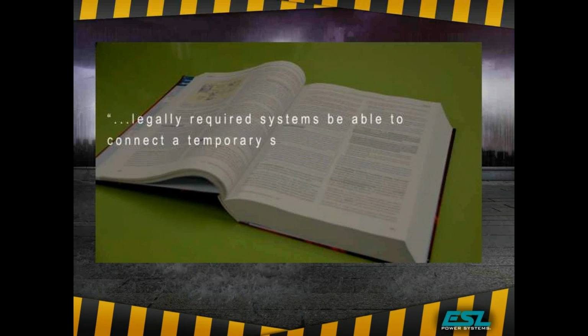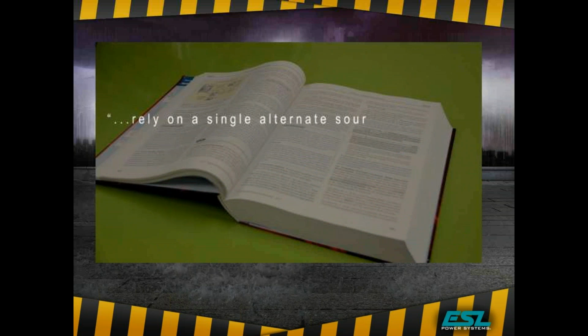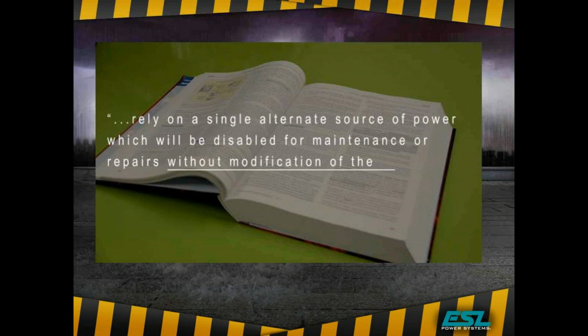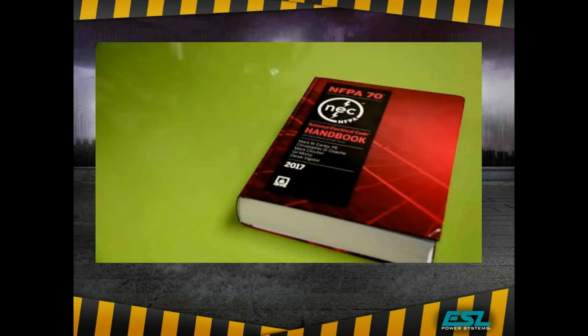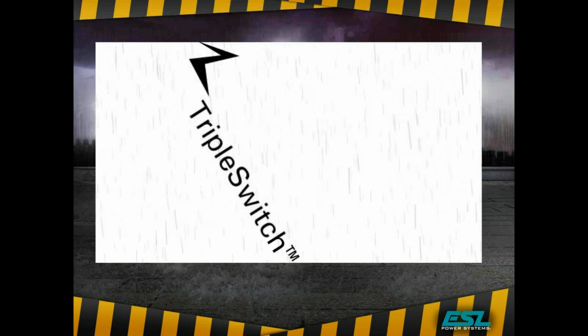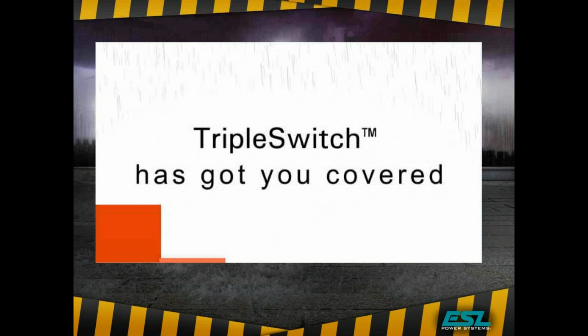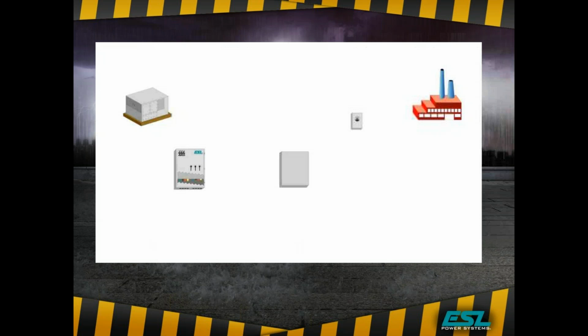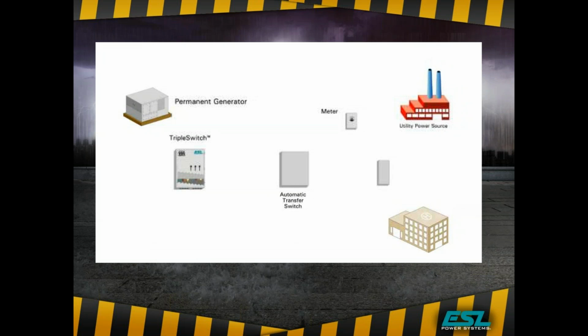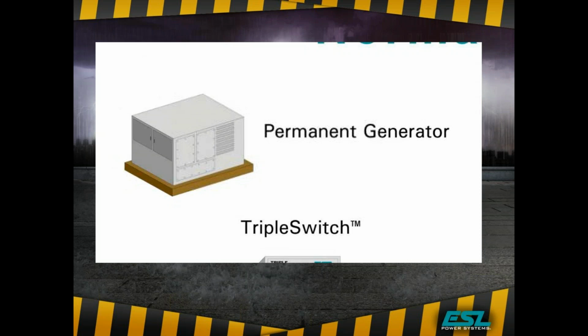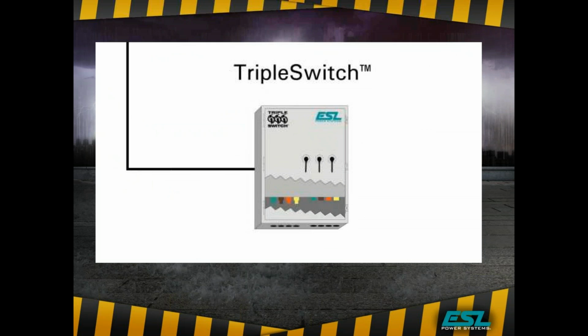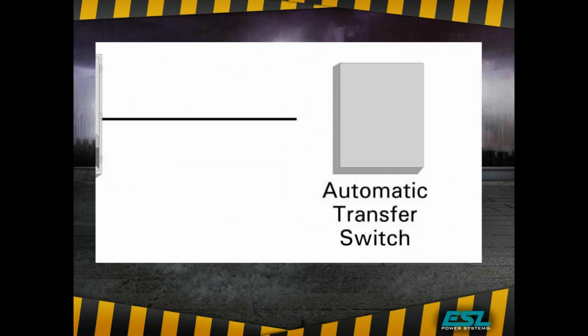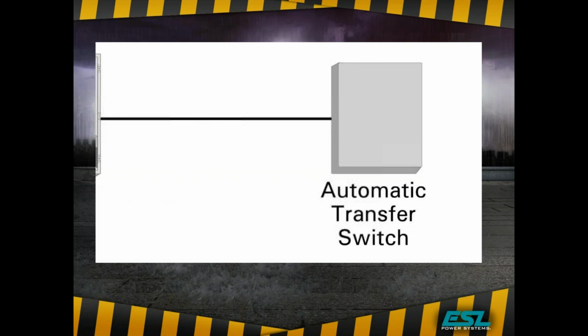able to connect a temporary source of power for emergency systems that rely on a single alternate source of power, which will be disabled for maintenance or repairs without modification of the permanent system wiring. Well, when used in conjunction with an ATS, the triple switch has got you covered. ESL's UL 1008 listed triple switch provides operating functions during various conditions. When first installed, the permanent generator is hardwired into ESL's triple switch, and the output from the triple switch is hardwired to the facility ATS.